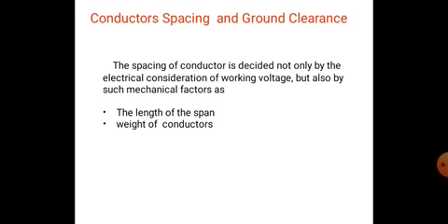Clearance is more in the residential area, where the density of trespassers is more. That is, it depends upon the locality of the transmission lines. If the lines are in an open area, the conductor spacing is more in order to avoid short circuit due to windage, and the clearance is more in a residential area where the density of trespassers is more.